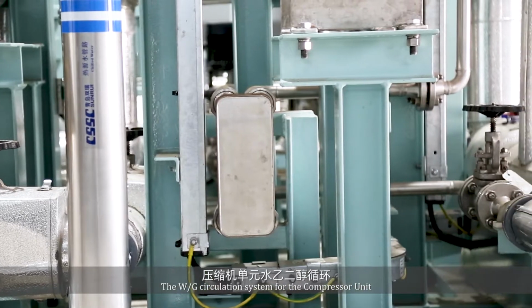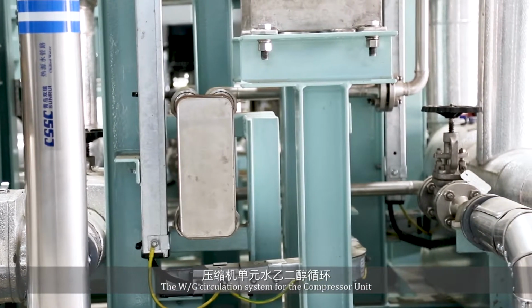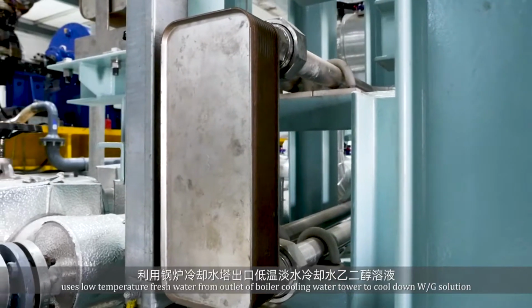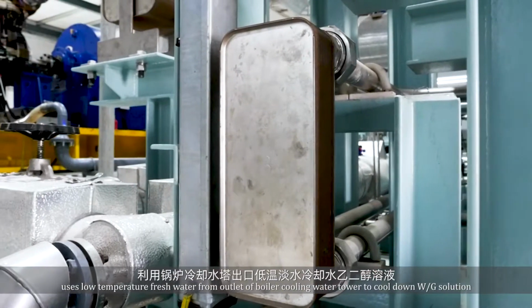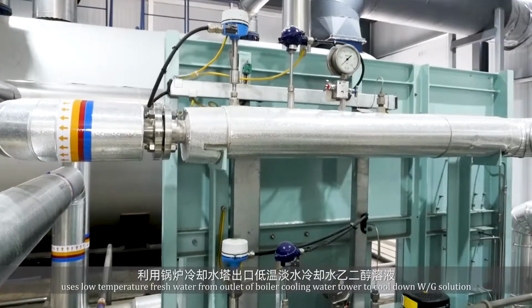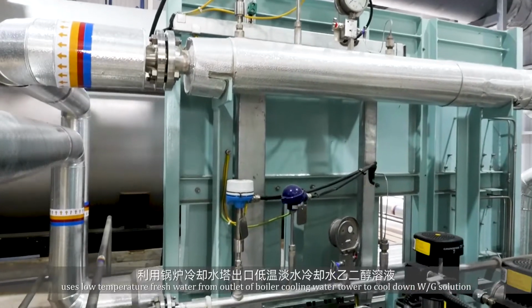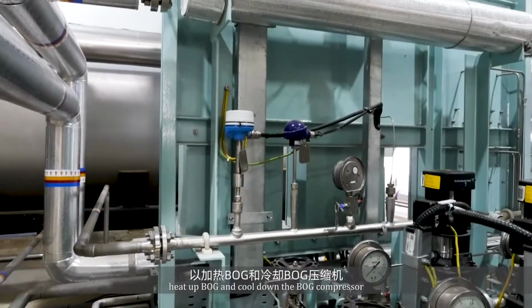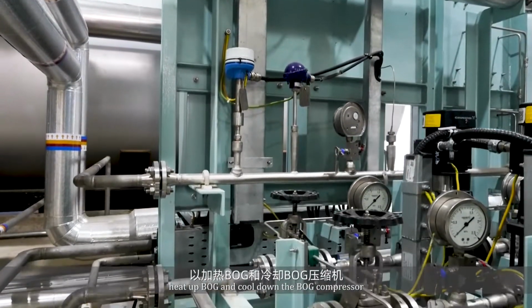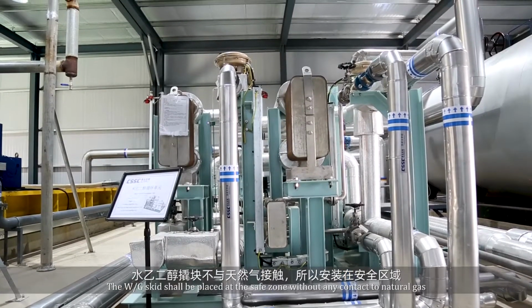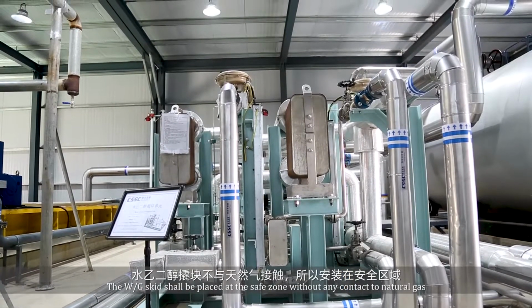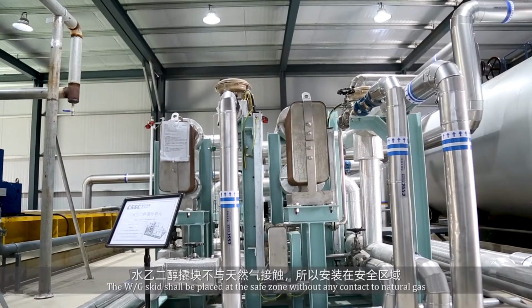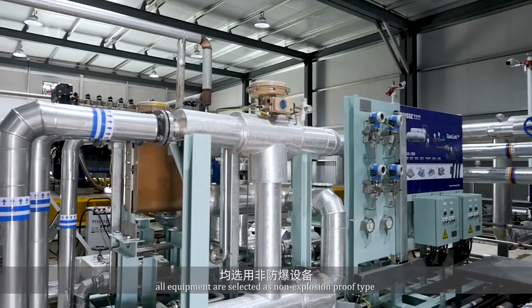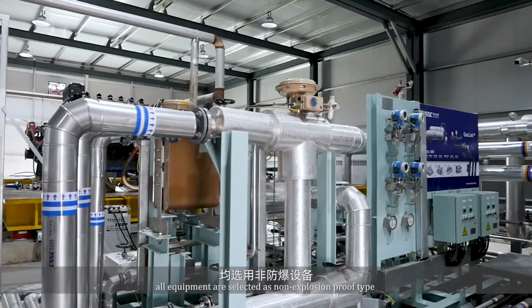The WG circulation system for the compressor unit uses low-temperature fresh water from the outlet of the boiler cooling water tower to cool down the WG solution, heat up BOG, and cool down the BOG compressor. The WG skid should be placed at the safe zone without any contact to natural gas. All equipment is selected as non-explosion proof type.